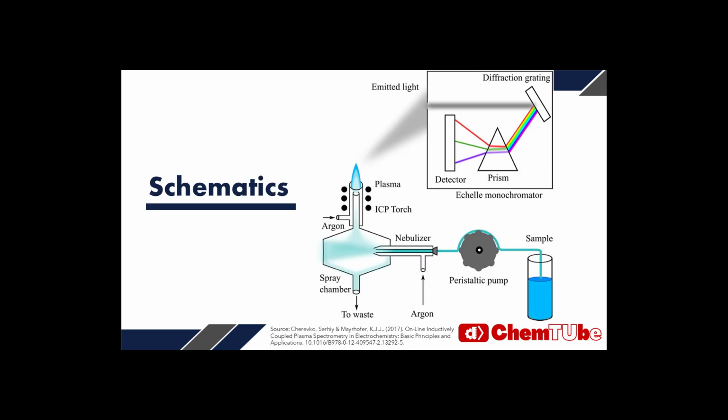For this technique, the sample should be either in the form of liquid or gas, because an aerosol has to be created from it. This is why solid samples require additional steps to turn them into an appropriate state. The prepared sample is injected into the machine. It is converted into an aerosol from which only the smallest droplets are allowed to pass further. The spray chamber ensures bigger droplets are retained and don't cause inaccuracies in the measurement. The aerosol is passed to the plasma.